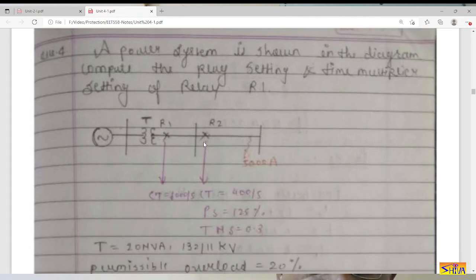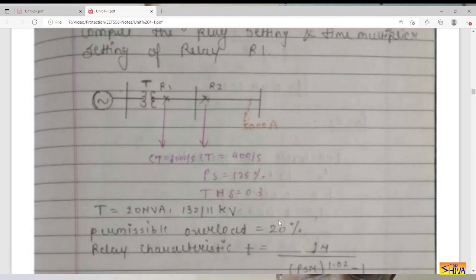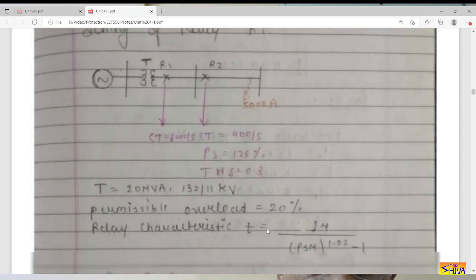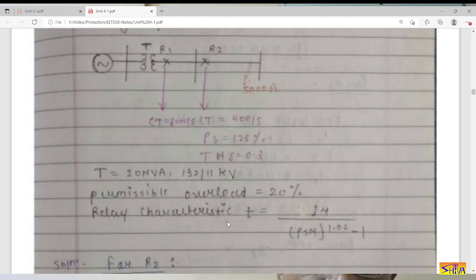For relay R2, the CT ratio is 400/5. For relay R1, the CT ratio is 1000/5. For R2, plug setting is given as 125% and its time multiplier setting is 0.3. Transformer rating is 20 MVA, 132/11 kV. Permissible overload is 20%. The relay characteristic is: T = 14 divided by (PSM^1.02 − 1).